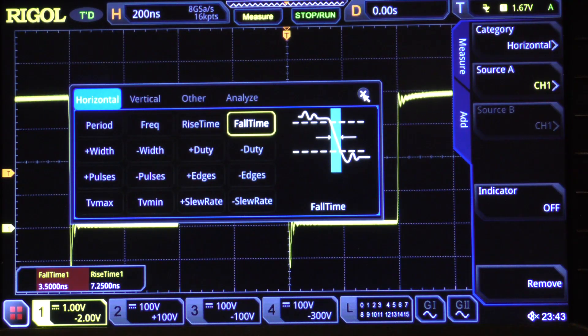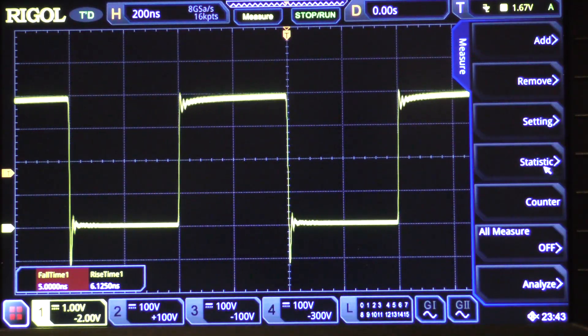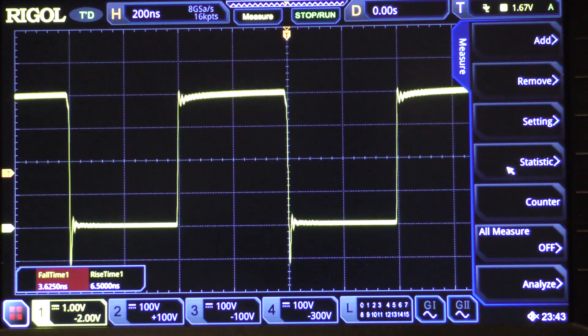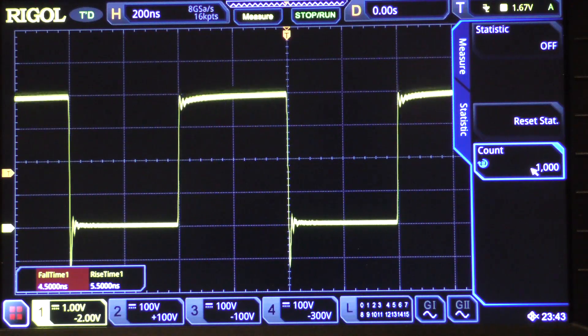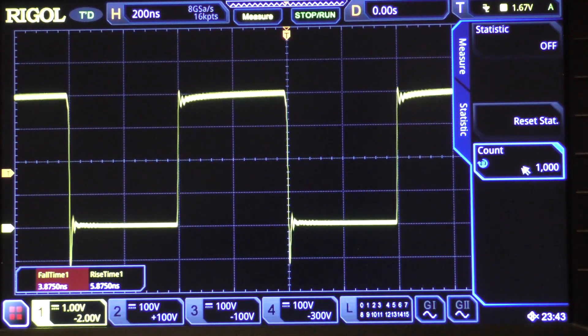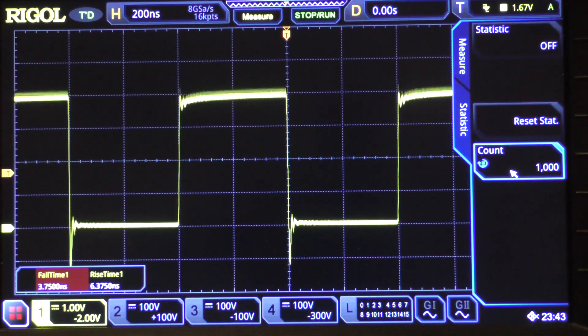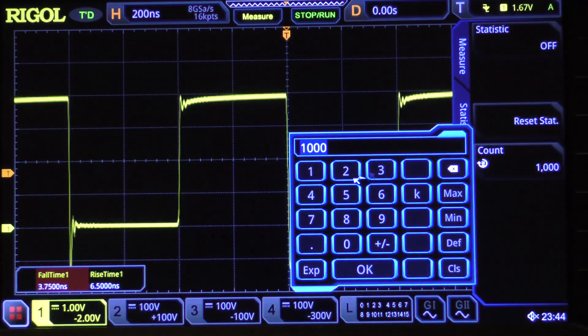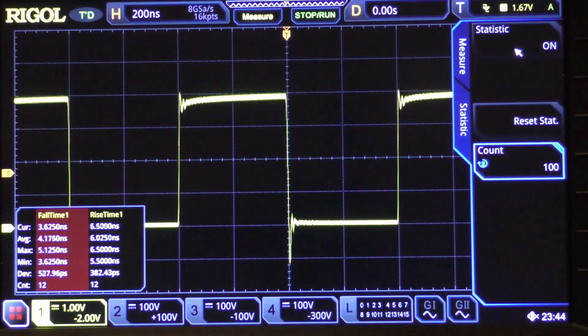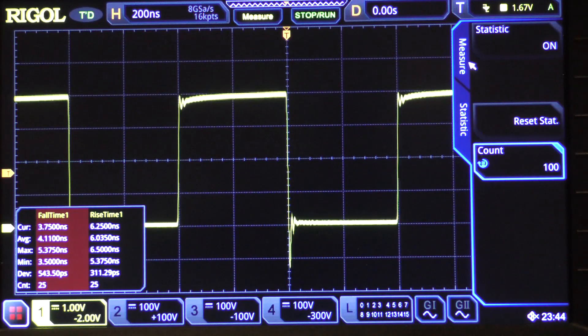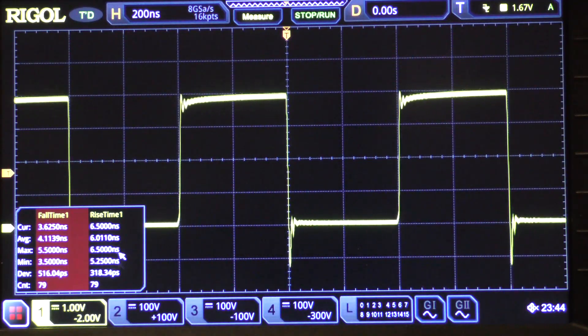You may notice down here in the lower left hand corner we now have a couple of boxes for fall time and rise time. Going back to the measure menu, you'll see a box here called statistic, so we're going to click on that. It's going to ask us for a count. It's generally a good idea to gather a thousand or more samples. I'm going to only do a hundred this time just to keep the video shorter. Then we're going to turn the statistics on and hit reset statistics.